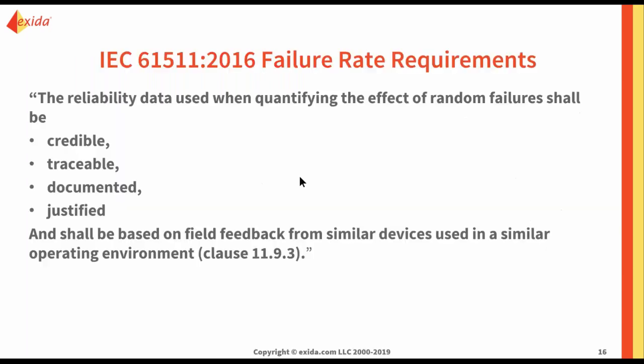There are a lot of assumptions here. In my opinion, that's one of the reasons why the editors of IEC 61511:2016 wrote some pretty strong language about failure rate data. It must be credible, traceable, documented, and justified. And more importantly, it shall be based on field feedback from similar devices used in a similar operating environment. That kind of fits in with the FMEDA technique — considering components, design strength, and operating environment stress. Reliability engineers know and understand this.